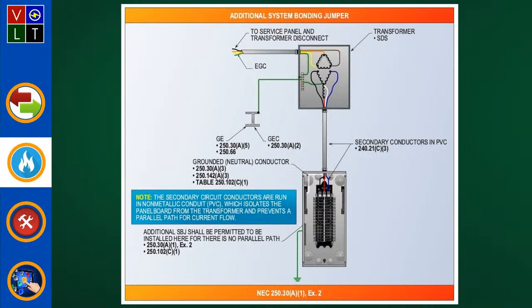So basically, what it's stating here is that the system bonding jumper shall not be required between enclosures for installations that comply with that type of installation. Wow. Okay. And that's why we went ahead and put this in here, because it is recognized in the exception. But basically what the section is really stating is that no parallel path can be set up in any way to be formed when you're installing any type of additional system bonding jumper at the equipment you're supplying by a separately derived system.